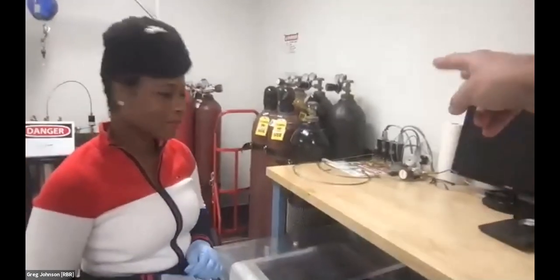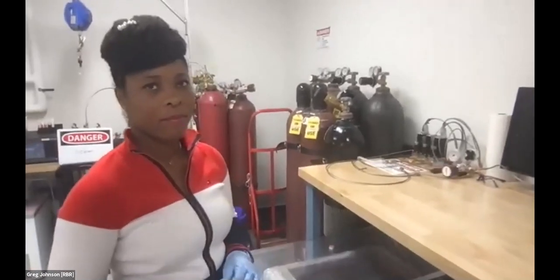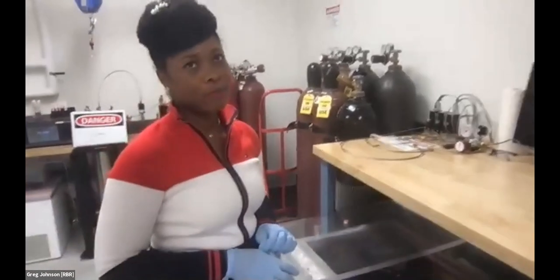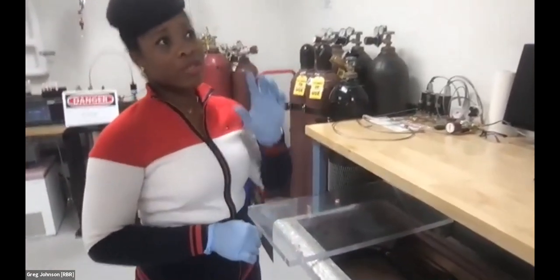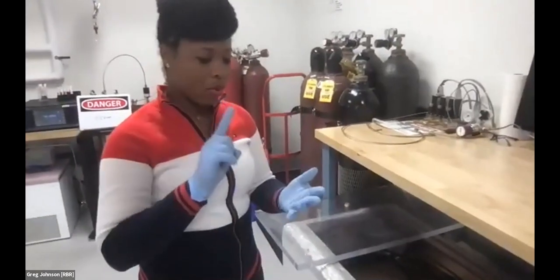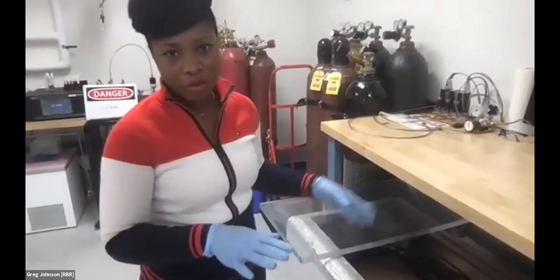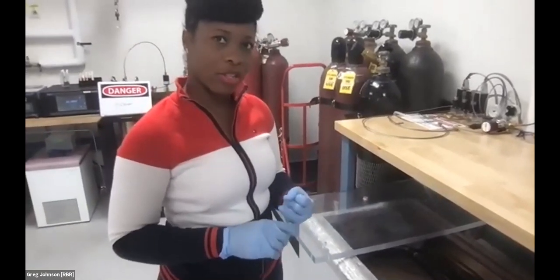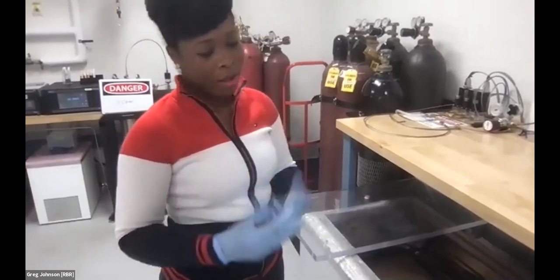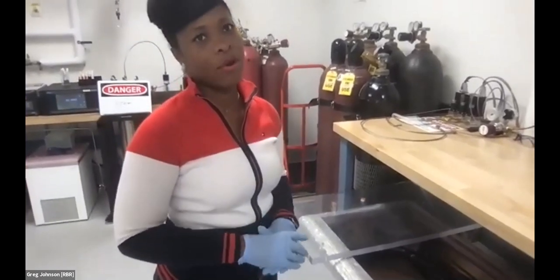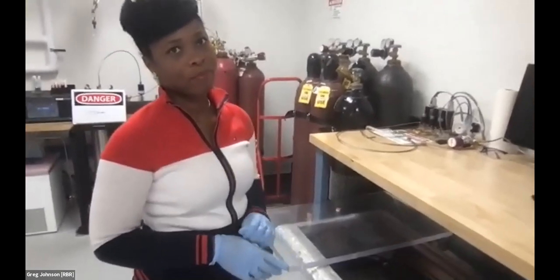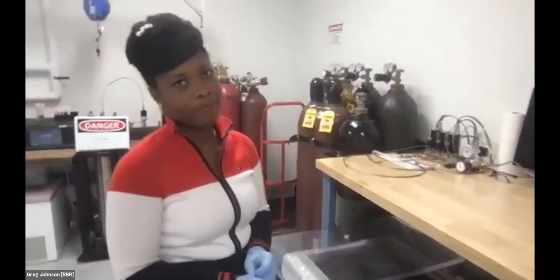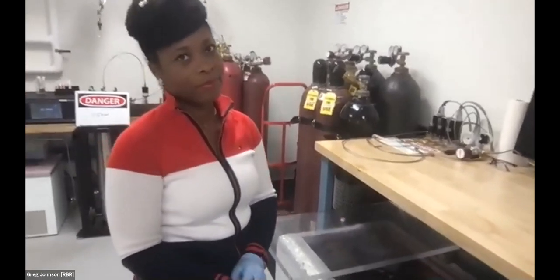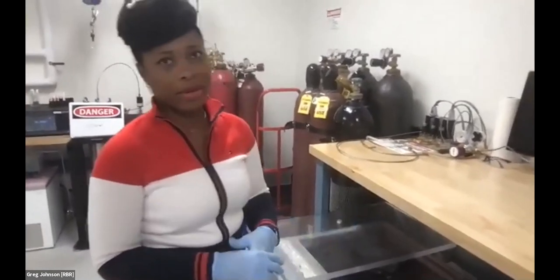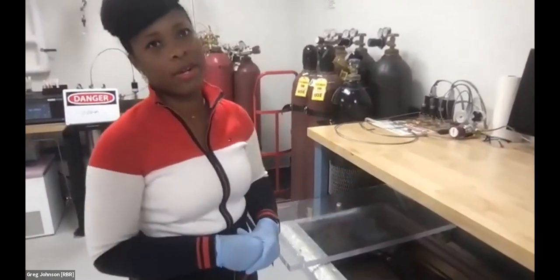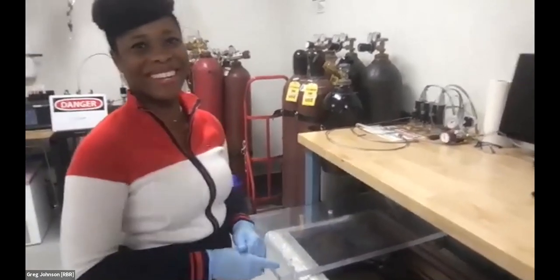And the MFCs, the mass flow controllers, allow us to change the blend of oxygen and nitrogen. Yes, they do. How many plateaus of oxygen do we use? We use 6. Zero, where there's nothing really, just nitrogen bubbling, and then 25% oxygen, 50%, 75%, 100%, 125% oxygen saturation. So almost 49 calibration points. Almost that. And then that surface that we generate is what we fit the polynomial to. Yes. Those coefficients then get stored into the sensor, and then off they go. Lovely.